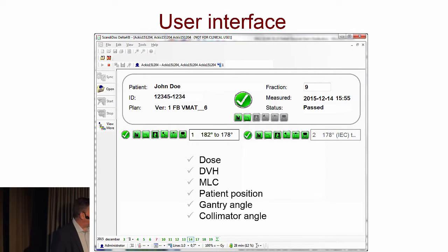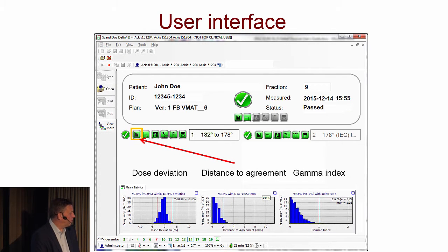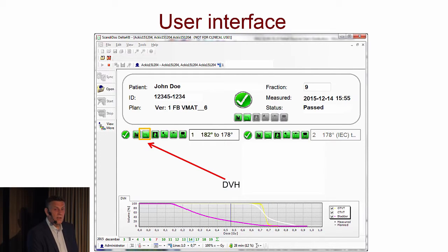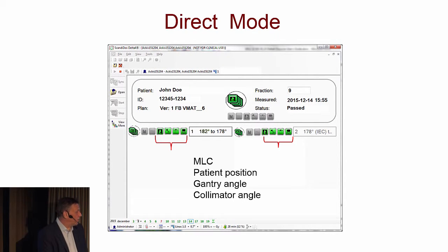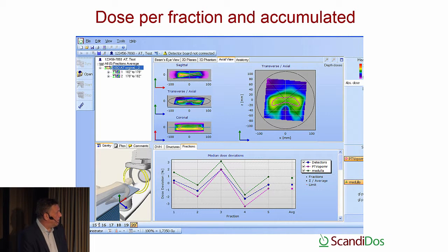So if all these are green, then you get the green status and you get a pass. If one of them is red, then it would be easy to just push the button, for example, the first one, and then you can look at the gamma index, the distance to agreement, and dose deviation. Or for clinically relevant data, the dose volume histograms. If you've only been running the direct mode, then you can look at the 4 parameters for the direct mode. It's also possible to look at the trends from fraction to fraction, from treatment session to treatment session for the patient.